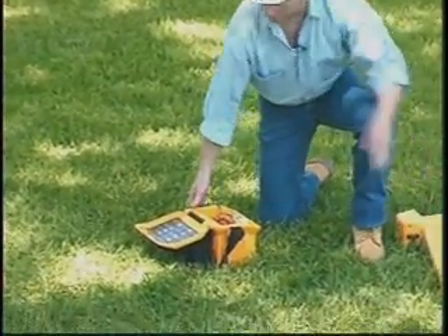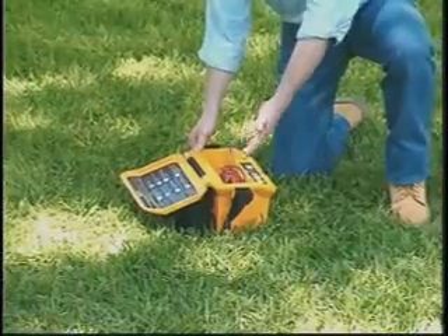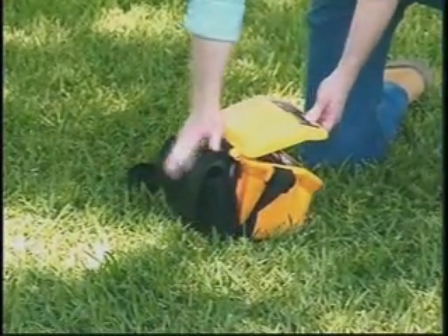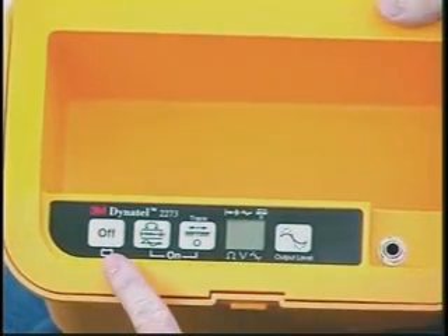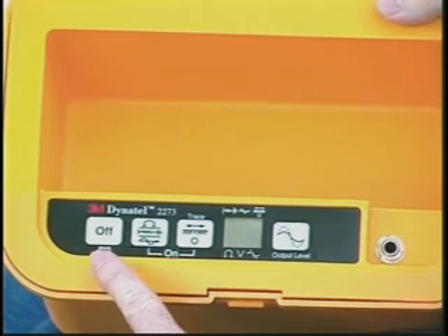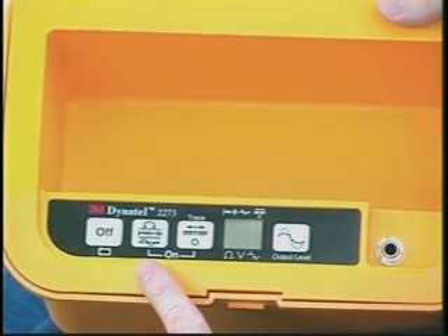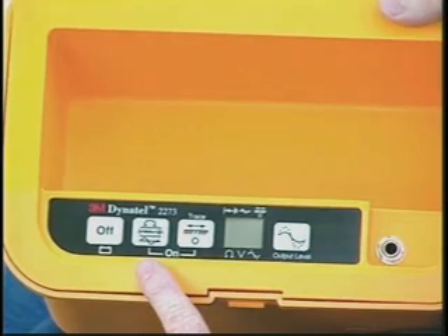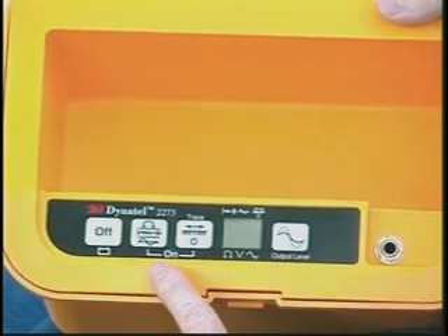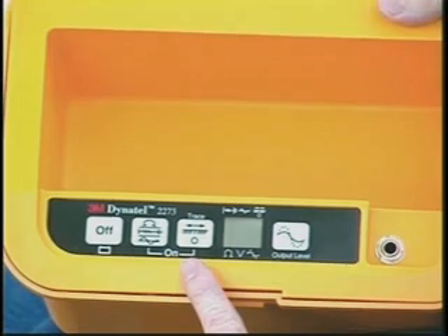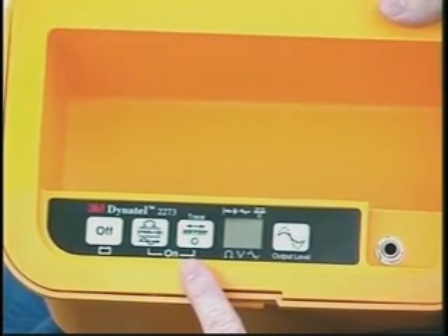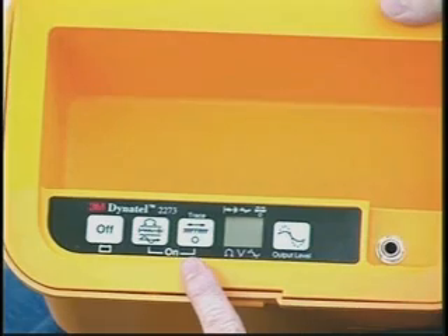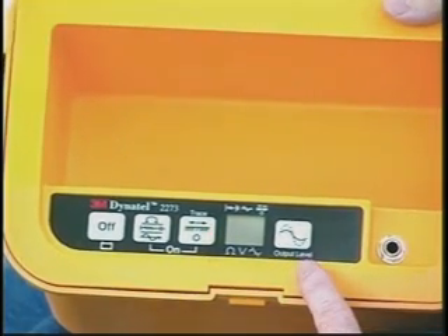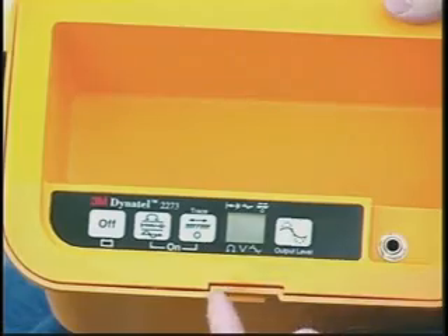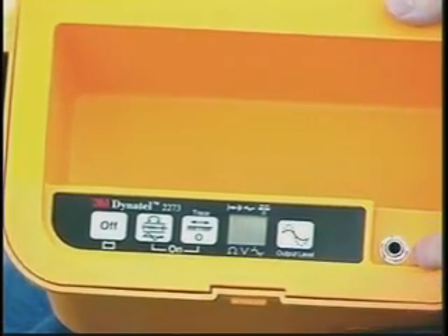The transmitter has storage space for cables, ground rod, and some accessories inside the case and in the external pouch. The switches are used to turn the unit off and to check the batteries, to turn the unit on in the ohms mode to check loop resistance and foreign voltage, and to put it in the fault or tone mode, to turn the unit on in the trace mode, to select one of 4 possible tracing frequencies, or to select all 4 frequencies simultaneously, and to select normal or high power level. There's also a display and an output jack.